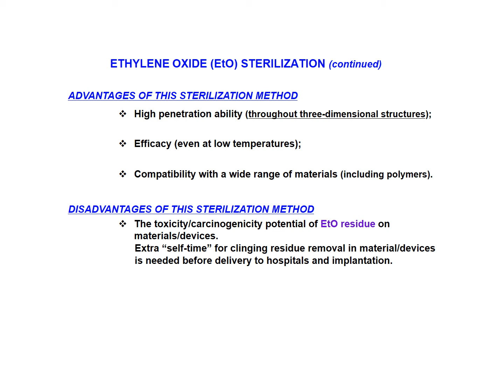The self-time is required and it must be taken into consideration by biomedical engineers who are in charge of this part of the operation and are responsible for delivering the requested implant devices to a particular client, a particular hospital. They need to take into account that extra time is needed to remove all clinging ethylene oxide molecules from the devices. In the past, there were some unfortunate incidents because the removal was not complete and implants with ethylene oxide residue were implanted and caused problems in patients.